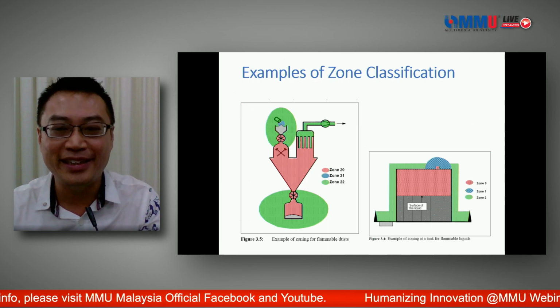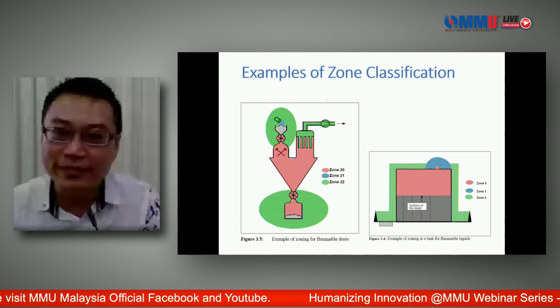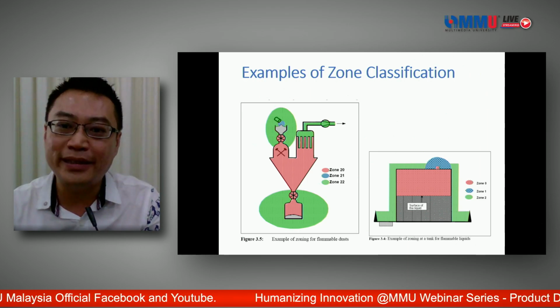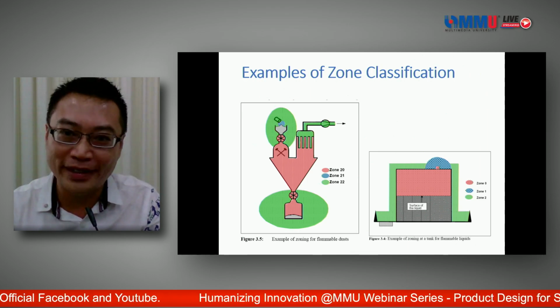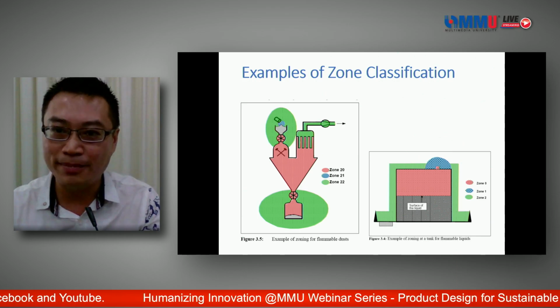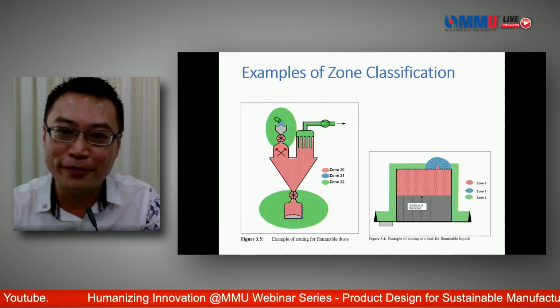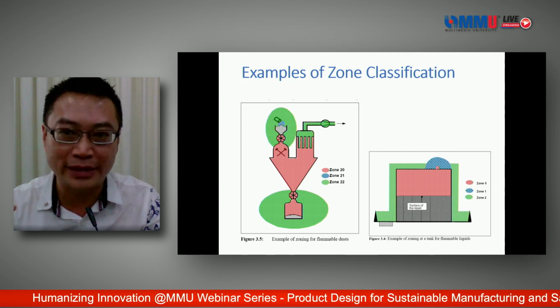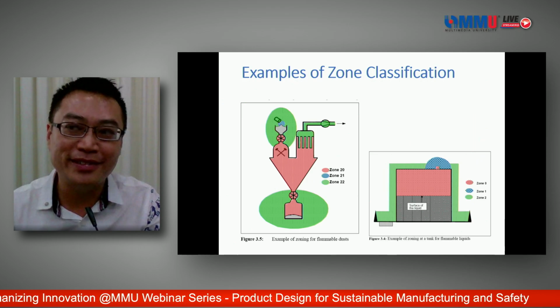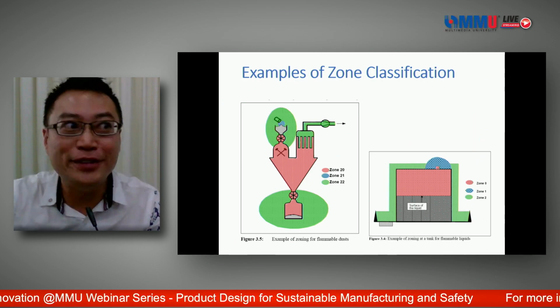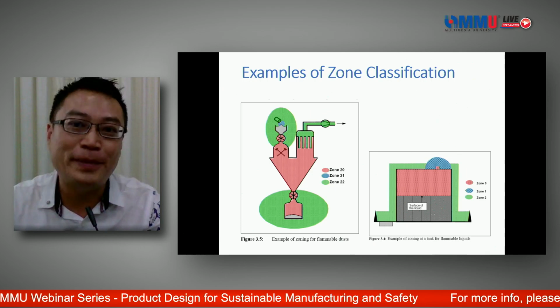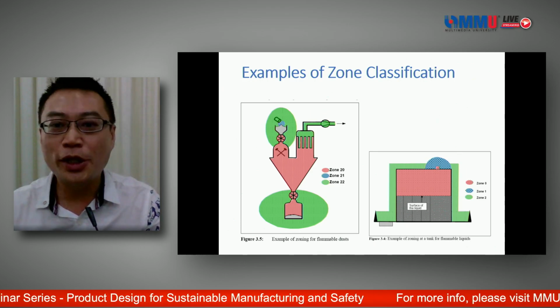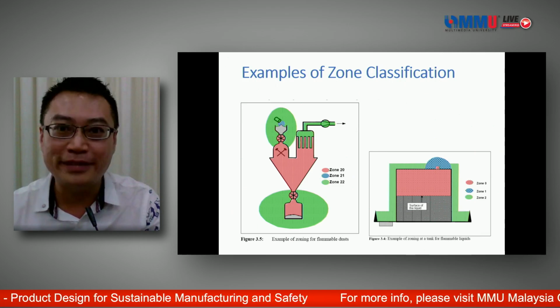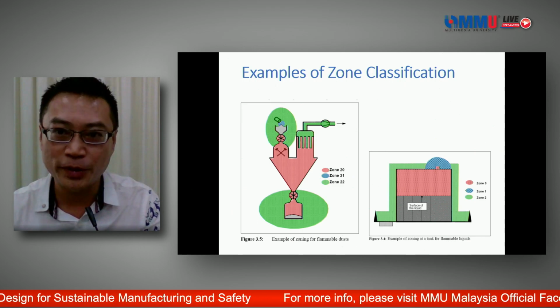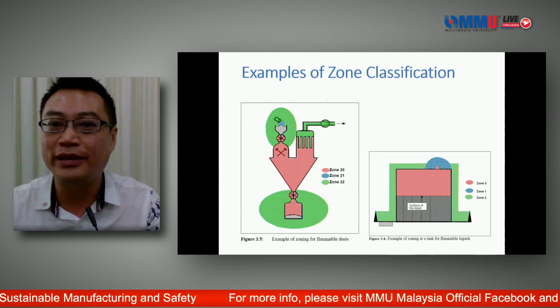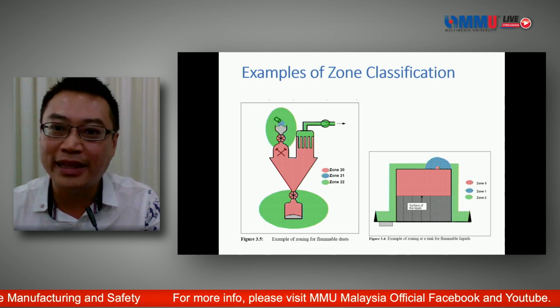In the dusty environment, you can see the green area before the dust enters the dust chamber, and a blue area just before that, meaning dust is present there occasionally under normal operation. For example, when you switch on the dust collector, dust will be present for that period. Inside the dust chamber, dust is always present, making it a dangerous zone 20. After the air is filtered, it goes out into the atmosphere where there's no more dust, so that's a green zone.